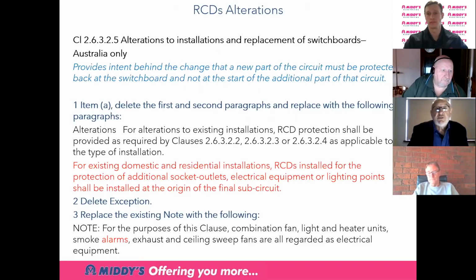In regard to alterations for installations and replacements, within this, we've actually changed and added under alterations the option: if you install a lighting point or electrical equipment and you're actually altering the circuit, then you shall install that RCD to protect that circuit at the origin of the final subcircuit, so at the switchboard.